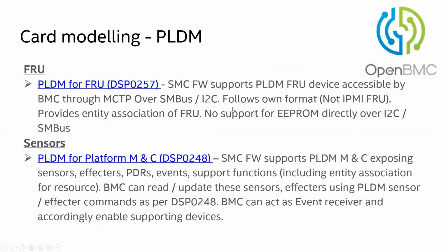Okay. So now coming to card modeling in terms of PLDM. The PLDM for FRU DSP257 specification talks about how a FRU has to be modeled. This is totally different from IPMI FRU, so it is not aligned with the IPMI specification. We have a different way, but this provides certain entity associations related to the FRU, and we can have multiple representations also.